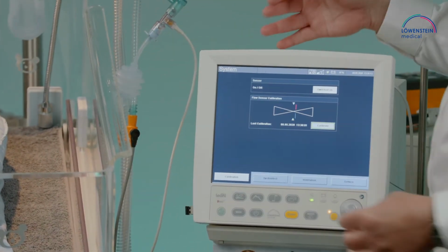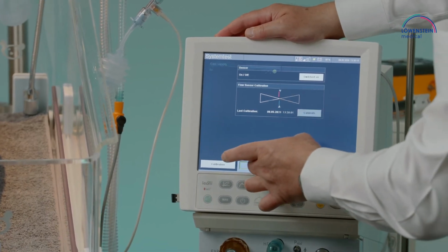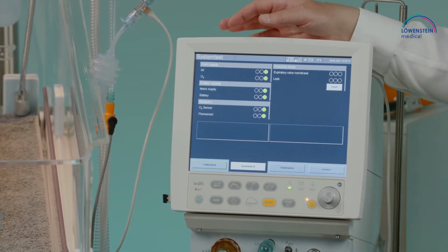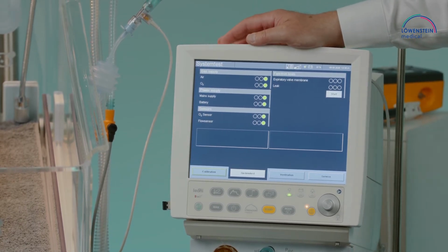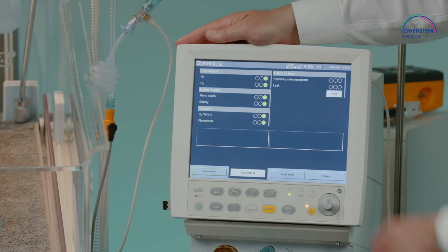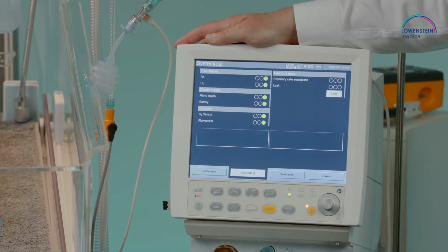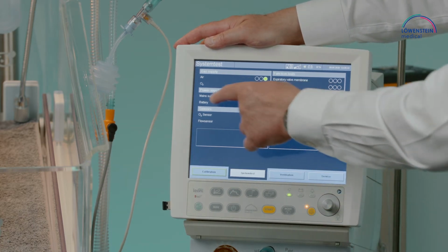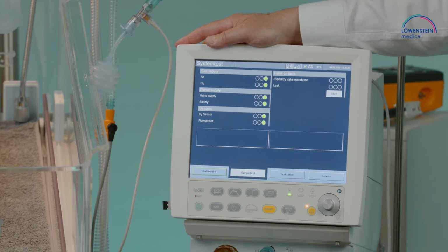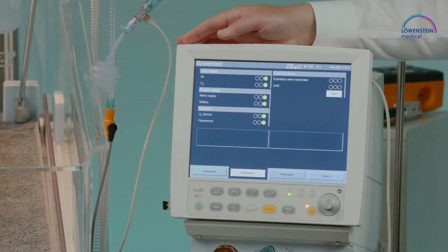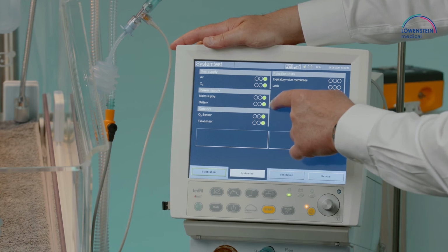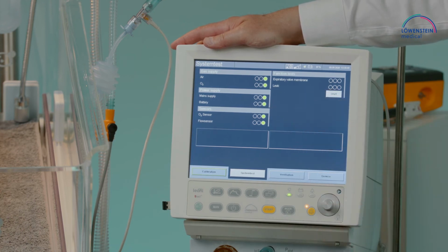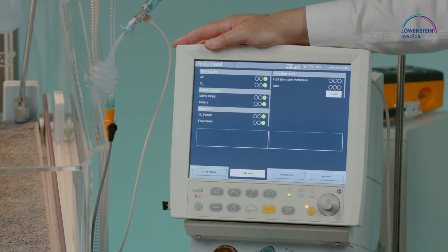We now can connect the test lung to the flow sensor and jump into the next screen. This is the direct system test. In the system test, we have displayed on the left side that we are connected to air and oxygen. The gas supply is connected, the pressures are there. The next point is about the connection to power supply. The mains supply is also on green with the traffic light system. Positive, it is working, it is present. The same for the batteries. The oxygen sensor is present and working, and the flow sensor is present and working.